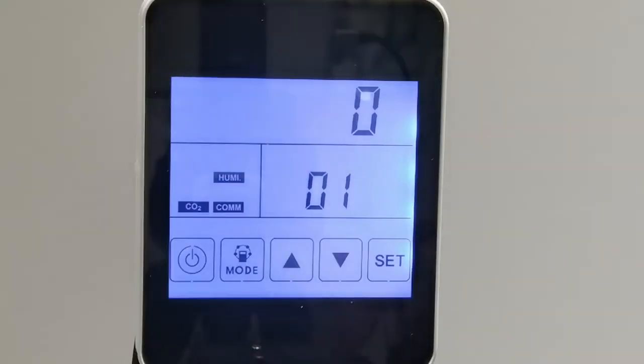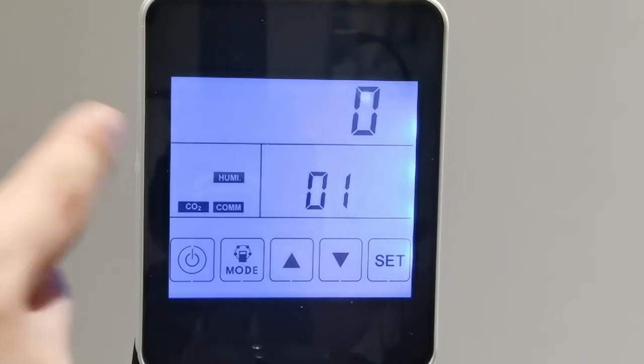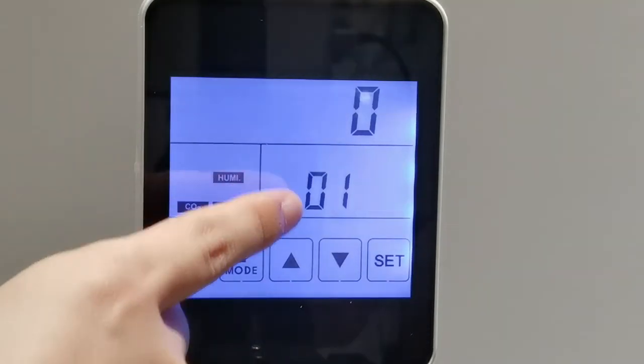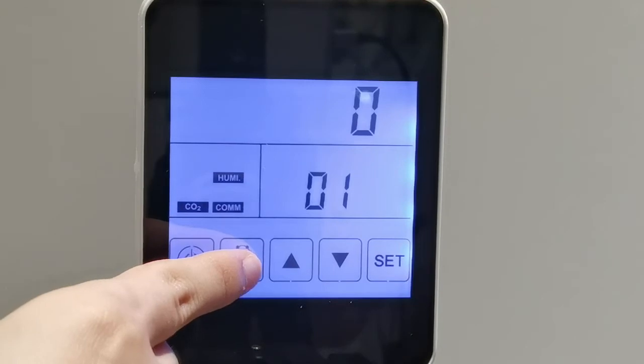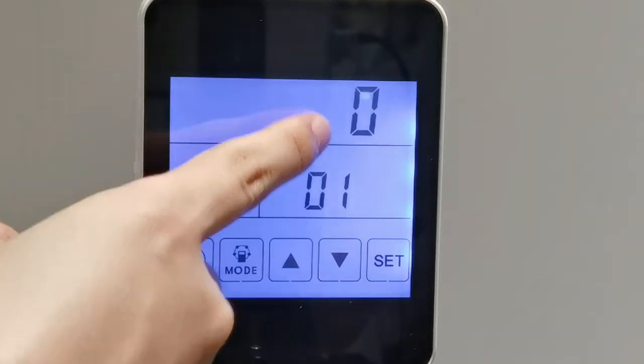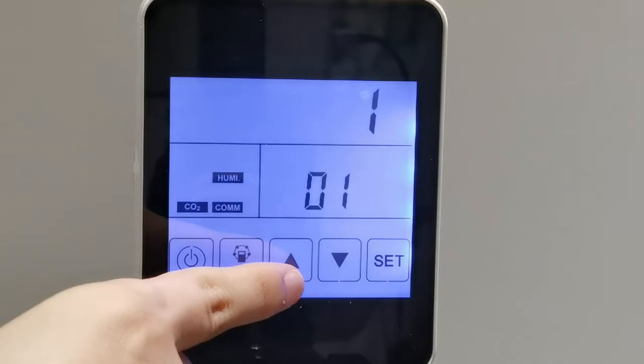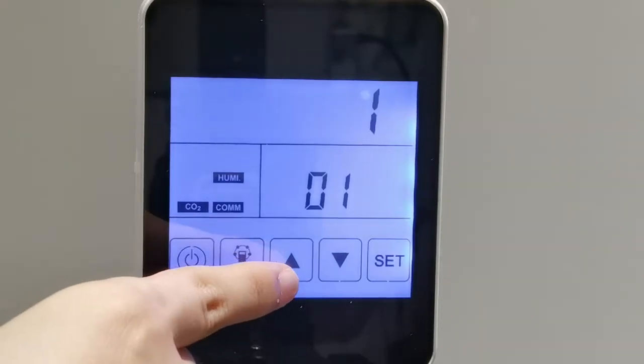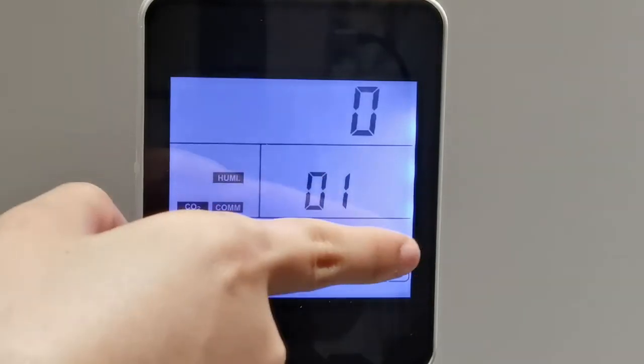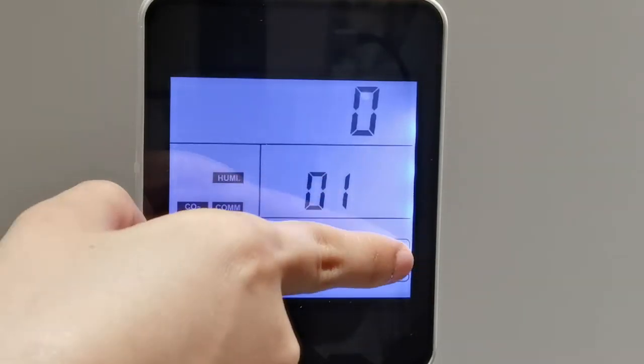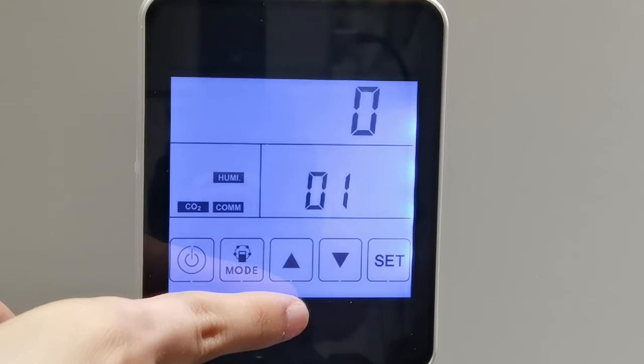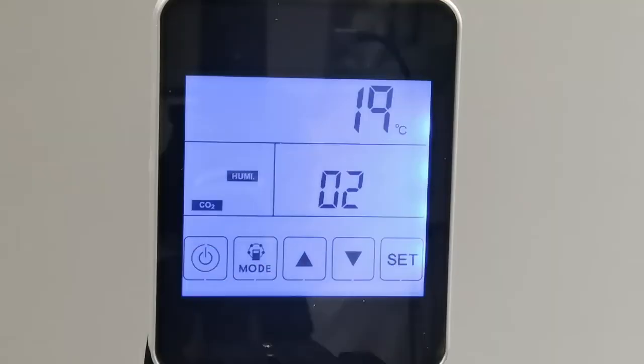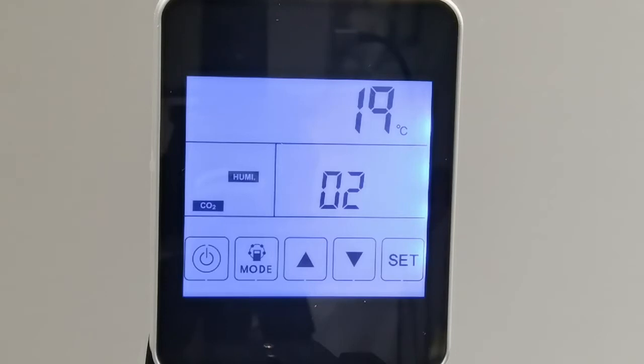Okay, 01 refers to the supply air electrical heater. It is available or not, meaning value 0 is for unavailable, 1 means available. Well, the default is 0. And after your ERV is connected to the electrical heater, you can choose value 1 to activate this function. Now we enter into parameter 02. 02 refers to the bypass opening temperature.